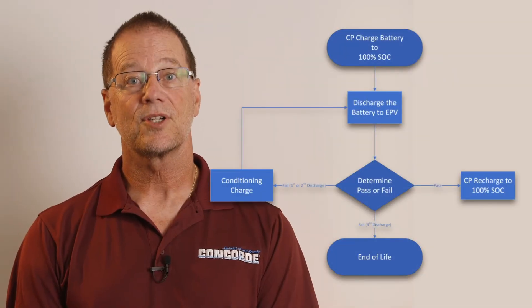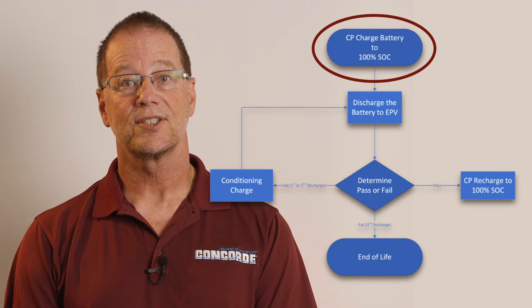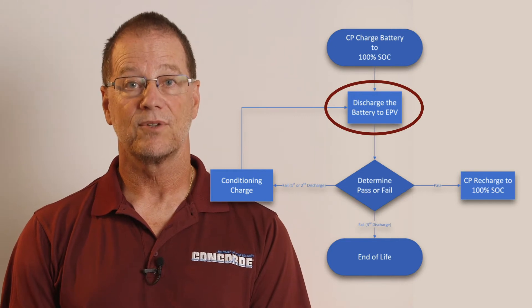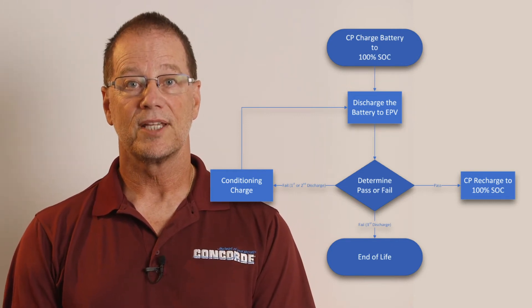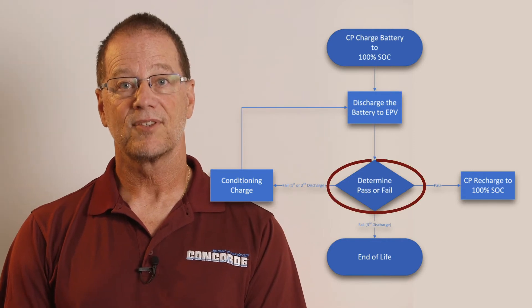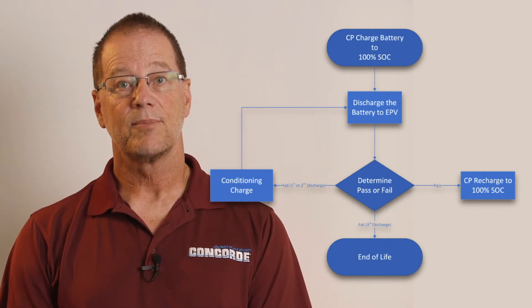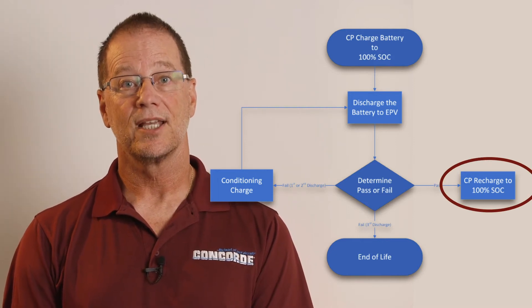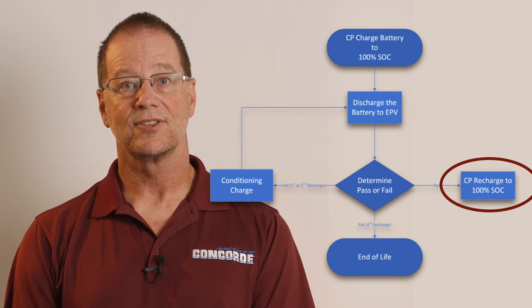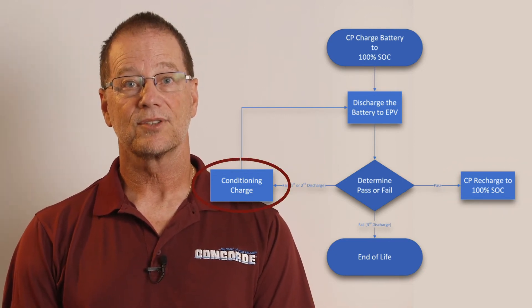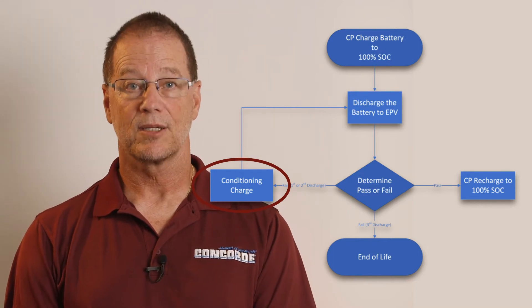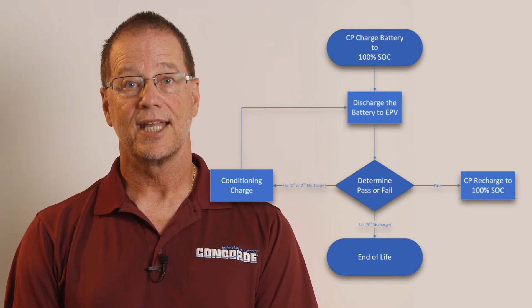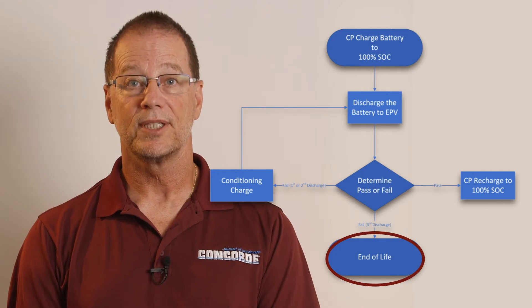First, the battery is charged at constant potential to 100% state of charge. Second, the battery is discharged at constant current to the endpoint voltage. Third, based on the measured discharge time, determine if the battery passes or fails. If the battery passes, recharge the battery at constant potential to 100% state of charge so it is ready for aircraft installation. If the battery fails, perform a conditioning charge and repeat the capacity test. If the battery does not pass after three discharge tests, it is considered end of life and should no longer be used.